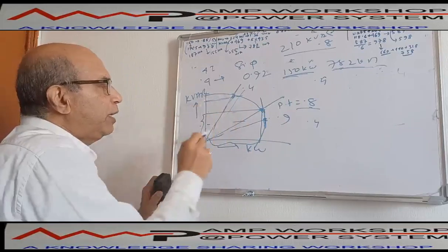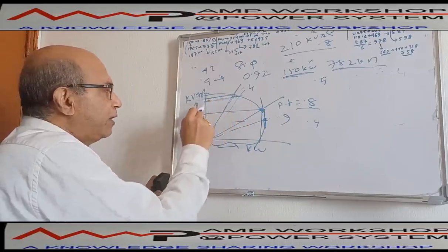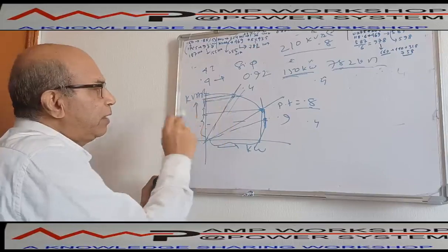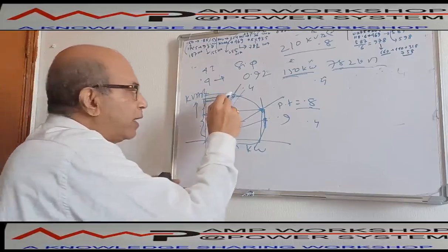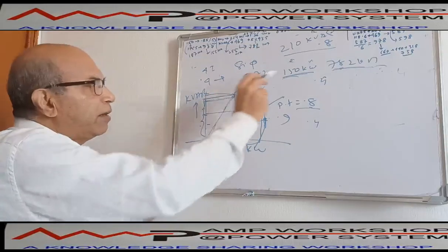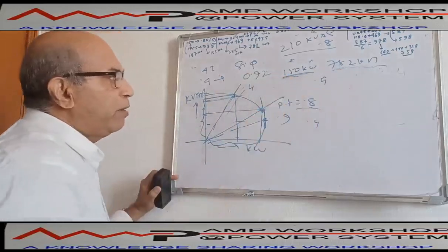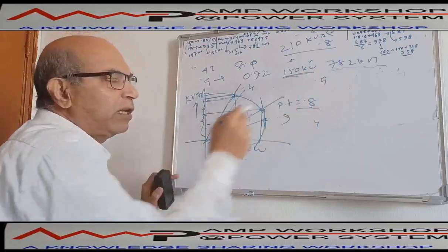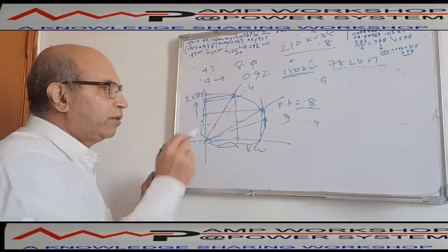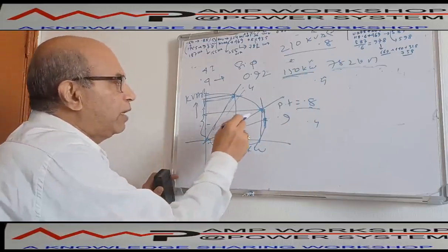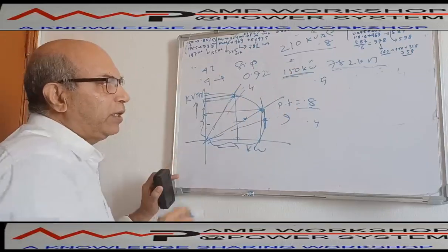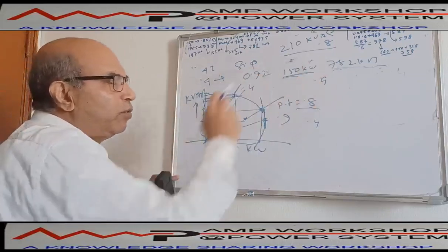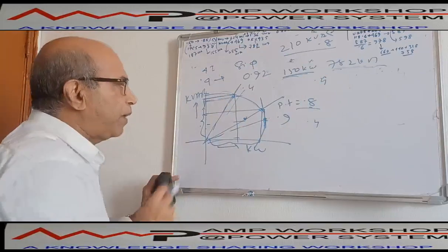When it is shifted over here, the kVA generation capacity automatically increases. You see here, it is within the capability limit, and kilowatt generation is reduced. In our case, at 782 kVA, our kilowatt requirement is very much less. It is only 35% more than the rated. So if the rated kilowatt is only in this area, it will be more than rated, but kVAR we need more. So here we can use this operation curve.